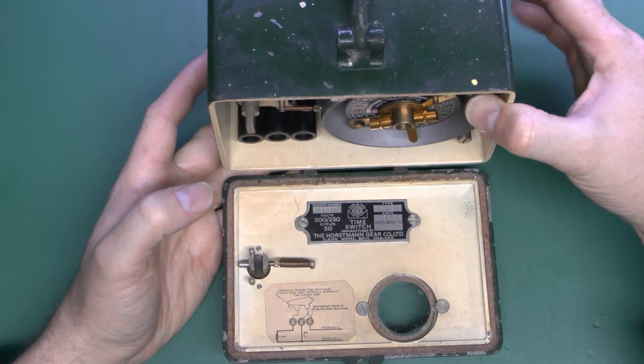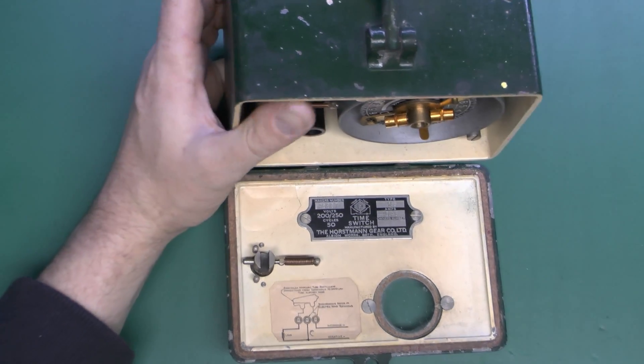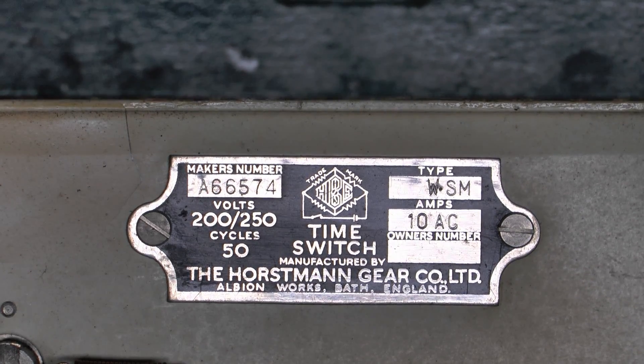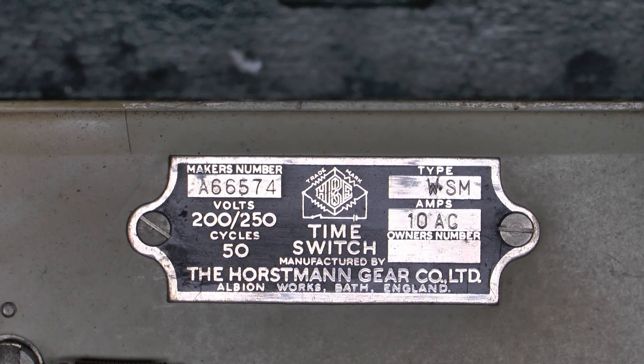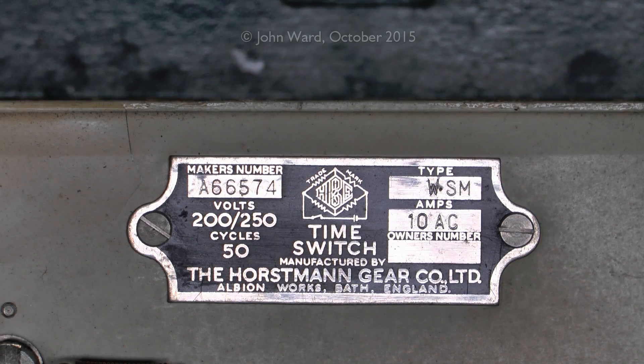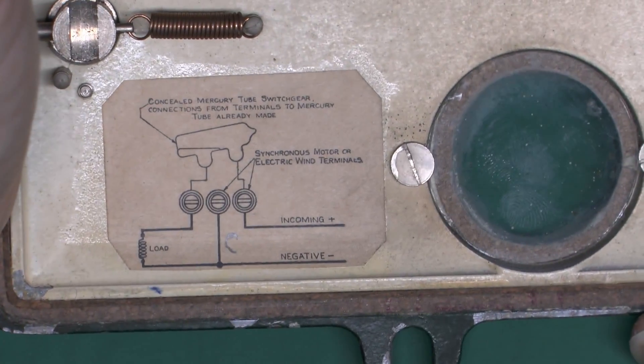Inside at the top we've got the actual clock and switch mechanism, and on the lower section we have the plate and label showing the wiring. The plate inside the front cover shows it's made by the Horstmann Gear Company Limited, Albion Works, Bath, England. 200 or 250 volts, 50 hertz. This particular one is a Type WSM, rated for 10 amps AC, serial number A66574. Horseman are actually still in business, but of course they don't make things like this anymore.